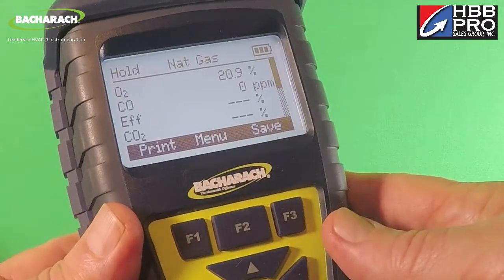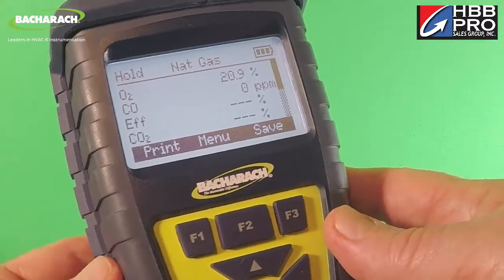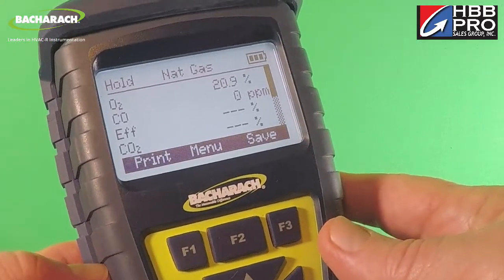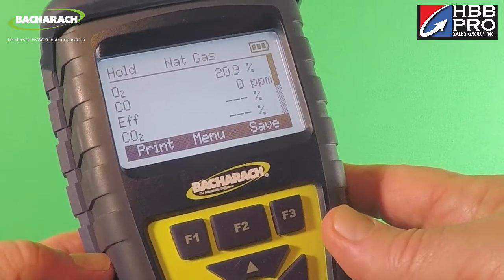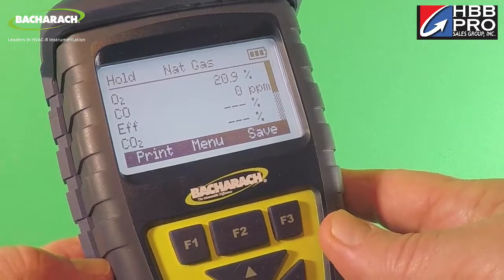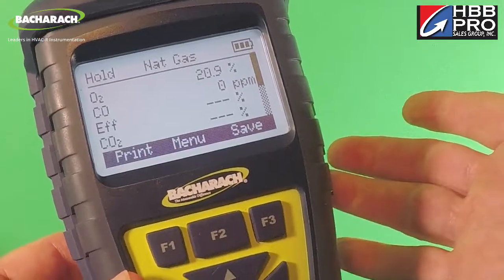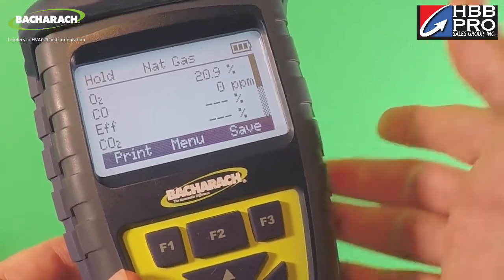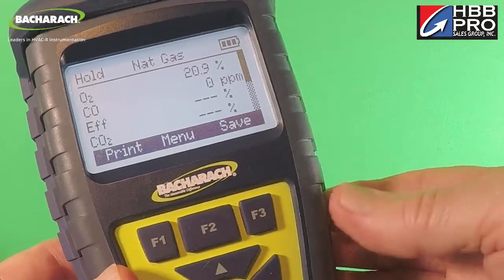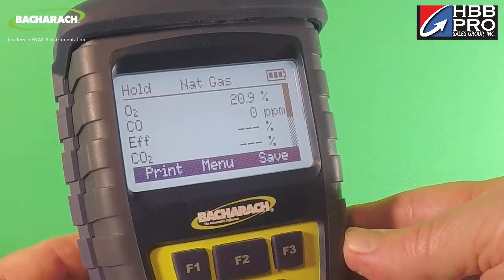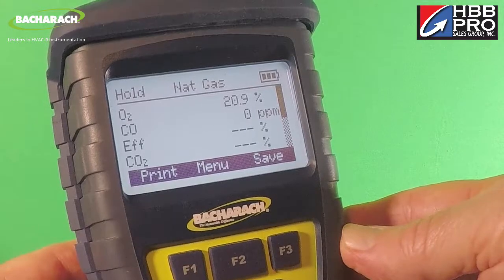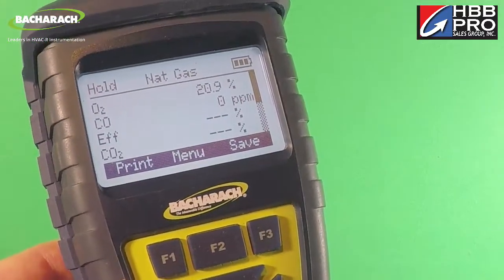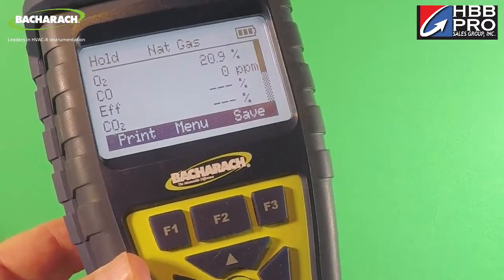It could also mean that the carbon monoxide sensor has reached the end of its useful service life, but frankly that's unlikely. Bacharach uses very good quality long life sensors. They should last many years. Although do keep in mind, like all manufacturers' carbon monoxide sensors, they do need to be calibrated typically every year. We'll talk more about carbon monoxide sensor calibration later.